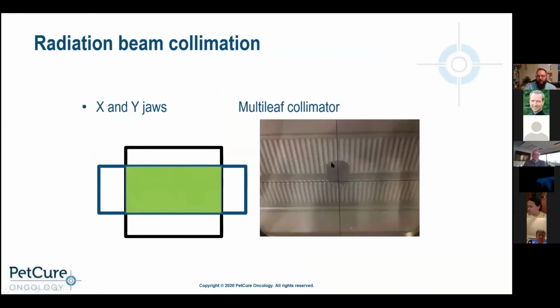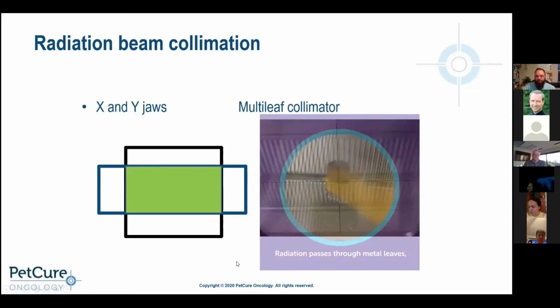Now with a multi-leaf collimator, these are individual lead leaves, and this would be what we call a dynamic 120 MLC. So 120, 60 on either side, individual lead leaves on motors that we can pull and shape the radiation field, thus creating a much smaller radiation field and also knocking off the corners, so they can really just treat this 3D tumor volume rather than cuboidal volume.